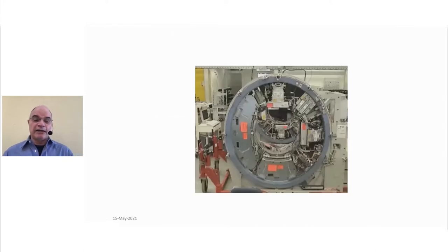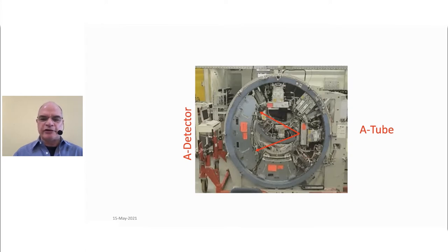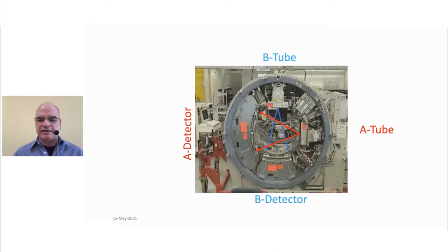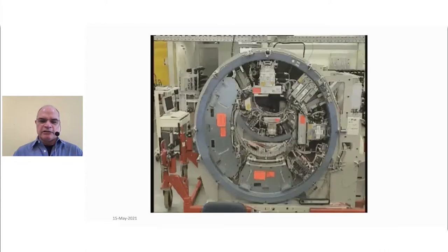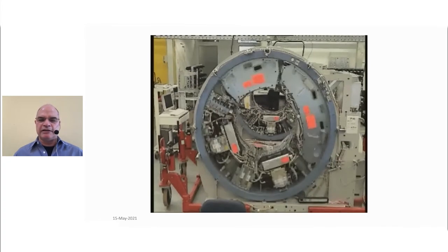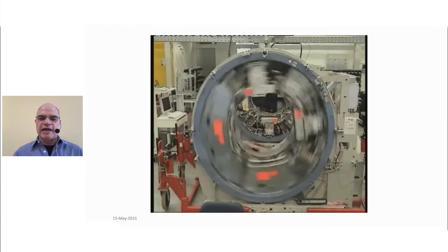This is an example of what I consider a technological marvel. Looking inside the gantry, you can see the A tube shooting x-rays to hit the A detector, and the B tube and B detector. The key thing about dual-source CT engineering is not only is this very dense with electronics, but all of this is done with no wires connecting it — it's all on the rotating frame. You have tube A, tube B, high kV tubes at 140 kilovolts, low energy detectors, all spinning up to 0.25 seconds per rotation. Truly amazing, without a single wire connecting any of the components.